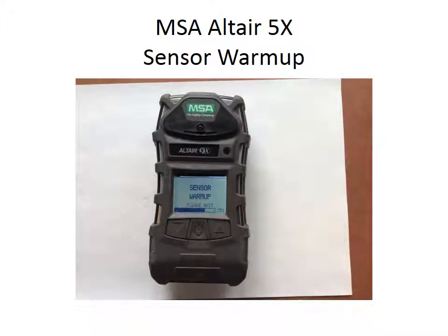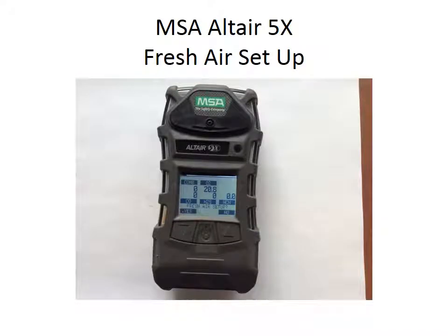Next screen you're going to see is the sensor warm up. Depending on how long it's been since the meter's been turned on, this takes anywhere from 30 seconds to a minute. If you've been running it for a while, and you turn the meter off and you turn it back on, it might just take a second to go through the sensor warm up. So that's that screen. Next screen you're going to see is a prompt screen. It's going to ask you fresh air setup, yes or no.